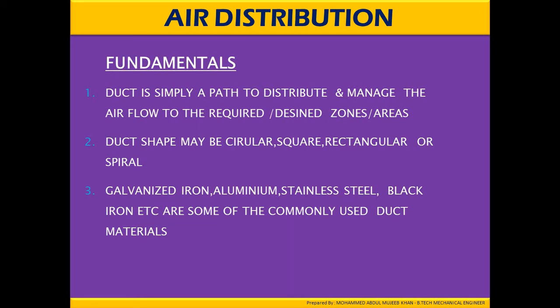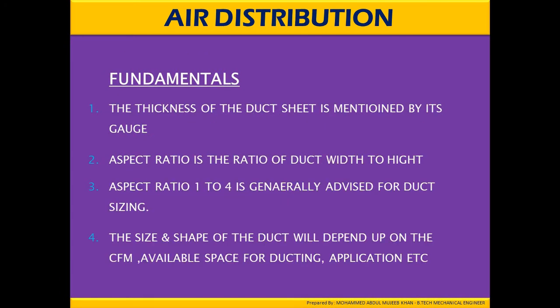Galvanized steel, aluminum, stainless steel, black steel, iron, etc. are commonly used duct materials. The thickness of the duct sheet is measured by its gauge. Aspect ratio is the ratio of the duct width to height, and an aspect ratio of 1 to 4 is generally advised for duct sizing. The sizes and shapes of the ducts will depend upon the CFM, available space for ducting, application, etc.